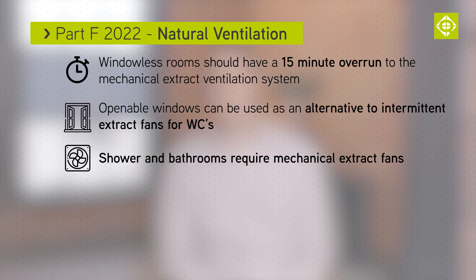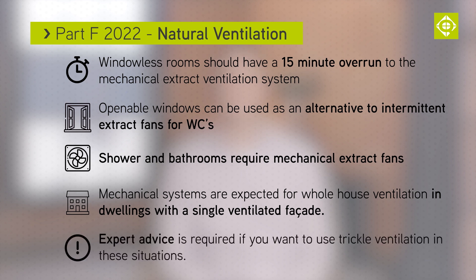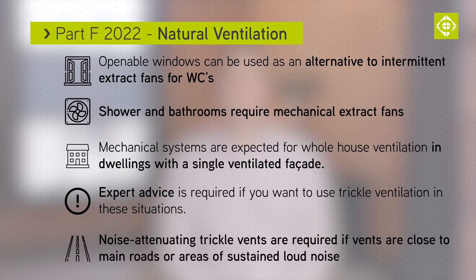For whole house ventilation in dwellings with a single ventilated façade, mechanical systems are expected. Expert advice is required if you want to use trickle ventilation in these situations. If fans and background ventilators are close to main roads or areas of sustained loud noise, noise attenuating trickle vents are required.